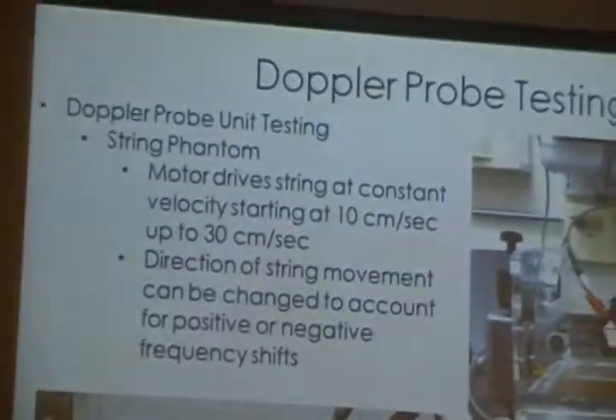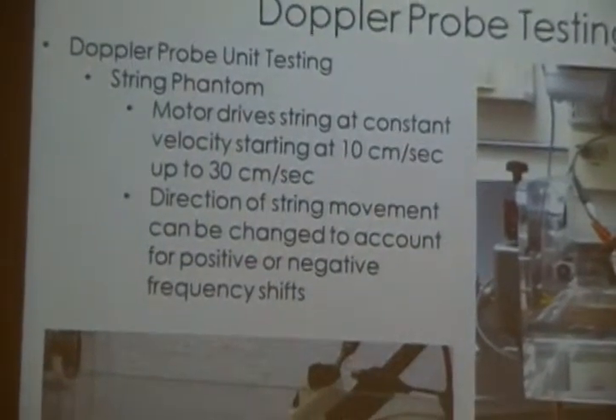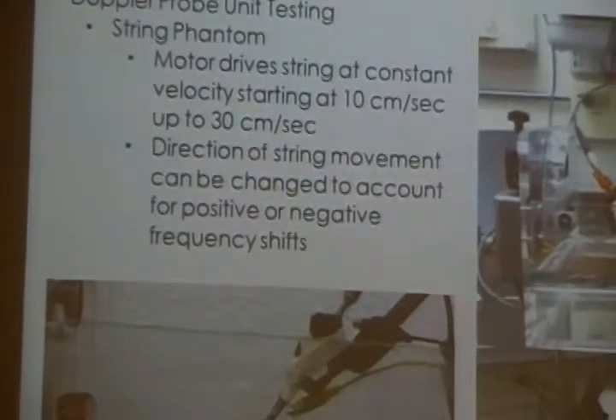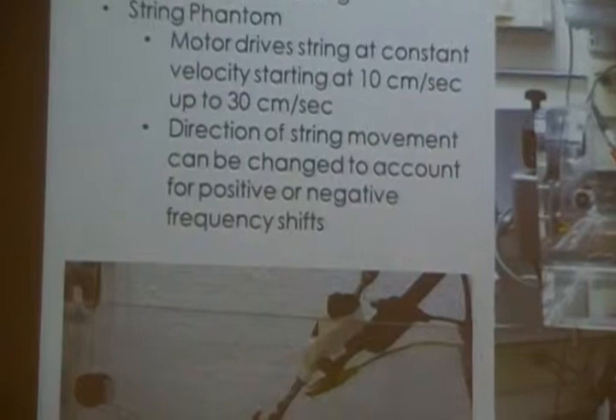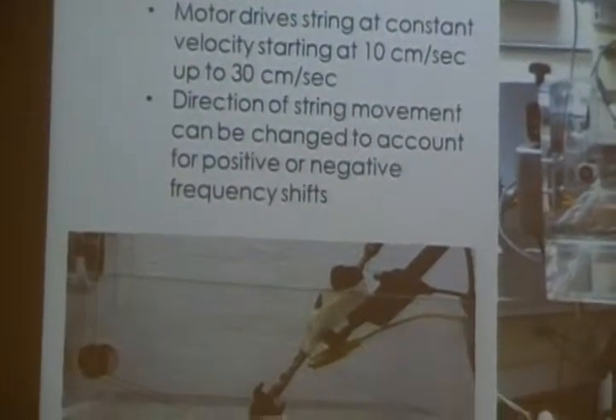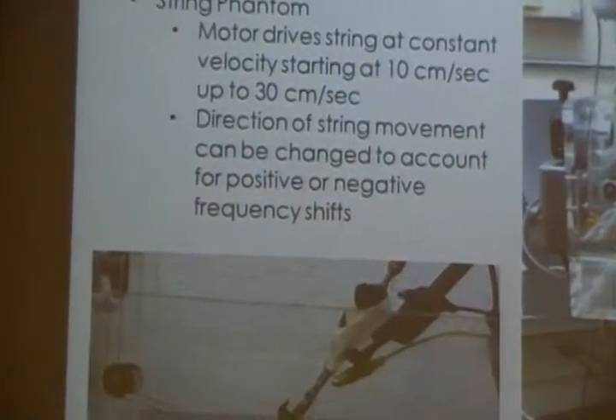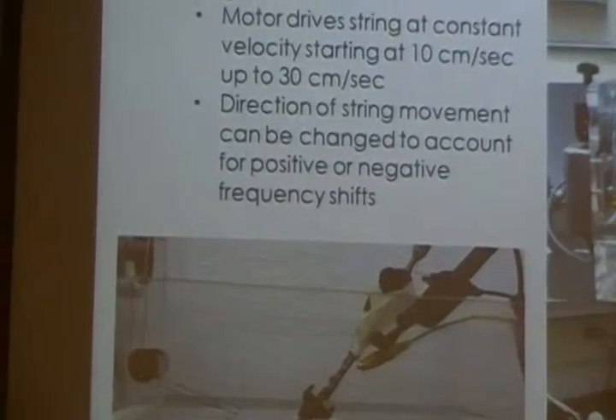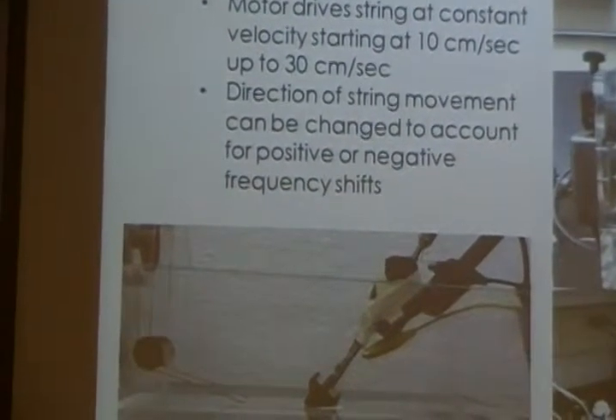Here you can see the unit testing of our probe, which was done on the string phantom setup. The string phantom is a motor-driven string which moves at a constant velocity. And the string can also be submerged in different mediums, such as water. We chose to do our testing in water because the speed of sound in water is approximately the same as the speed of sound in muscle.